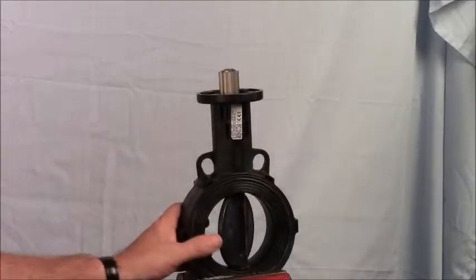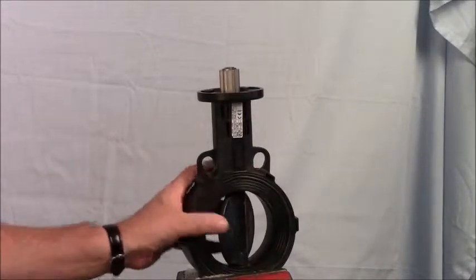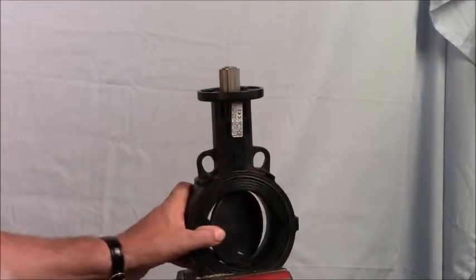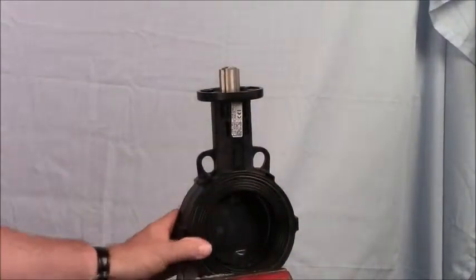So when mating to the valve, remember that the actuator is sent in the closed position but this valve is now in the open position. So we want to move the valve to very close to the closed position, or what we think is to be the closed position.